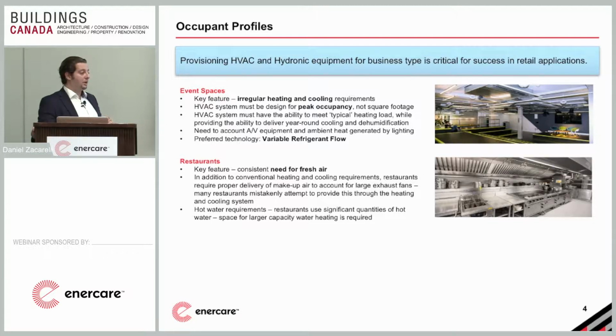So for example, water heaters and boilers, the more conventional type, bring in air as they need to combust the combustibles. And if it's under a negative pressure, it's not able to breathe. Imagine a room is sucking all the air out, and as you try and breathe in, you can't. As a human, you can't breathe in yourself. Equipment works in the same fashion, and that leads to heavy degradation of your equipment. Life cycles we see cut to less than half for these water heaters and boilers, for example.